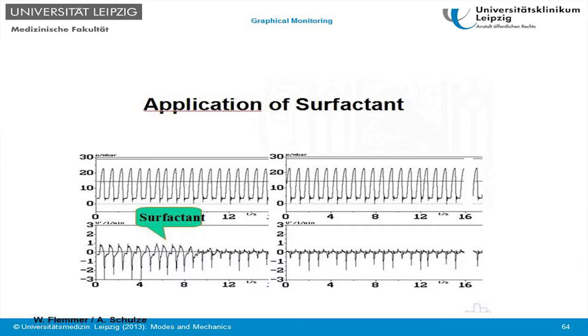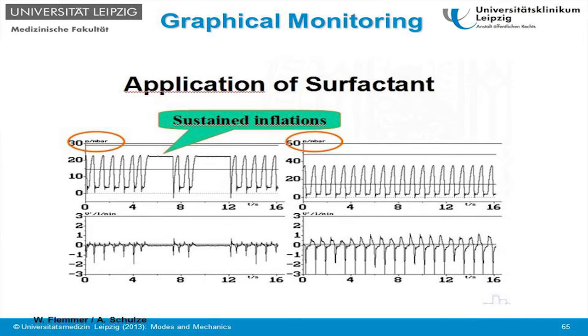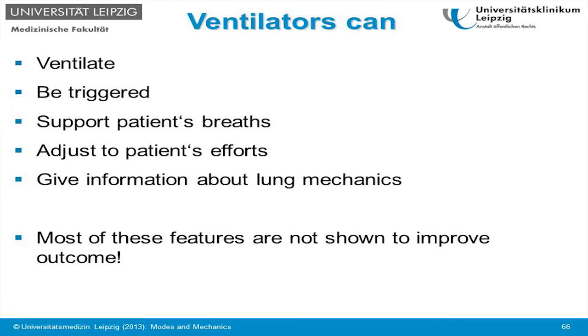Surfactant application can be monitored by a flow sensor. Surfactant has been instilled here, and we see a strong drop in tidal volume. So this is caused by the surfactant fluid causing airway obstruction, and you can see it right away and then respond to it by a temporary pressure increase to maintain tidal volume during the surfactant application and prevent the patient from getting a desaturation during surfactant application. You can also do sustained inflations and monitor the effect on the ventilator display.